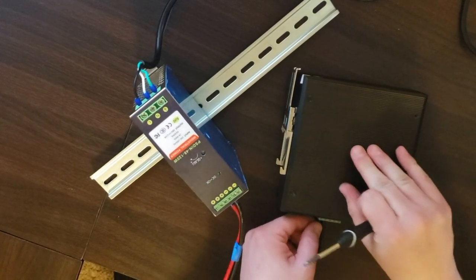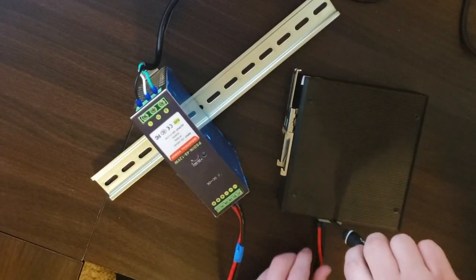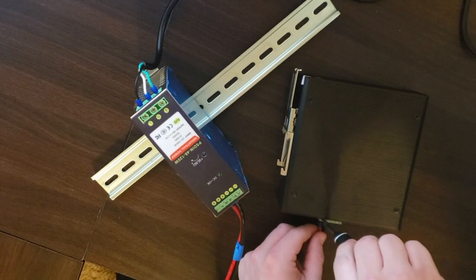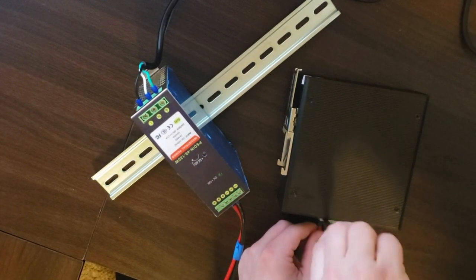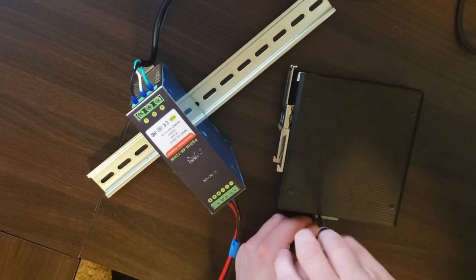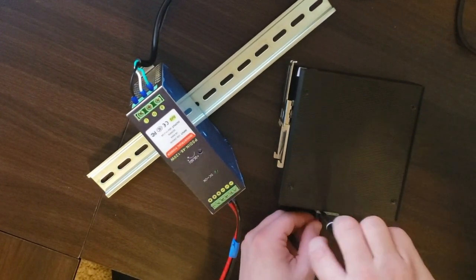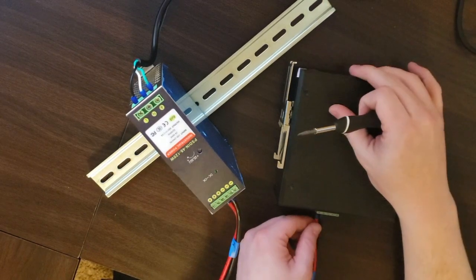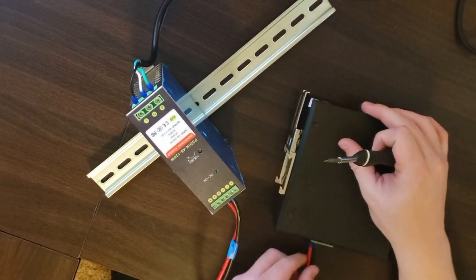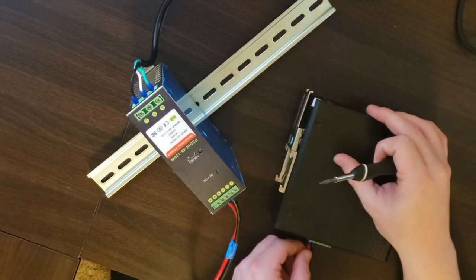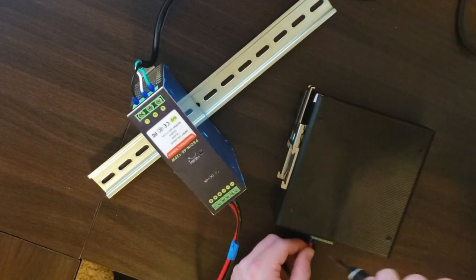There is a DC voltage adjustment on the front panel to make minor adjustments to the output voltage. Do not change single parallel switch position while the unit is powered up. Please make sure to disconnect power before changing the mode to avoid damage to the unit.